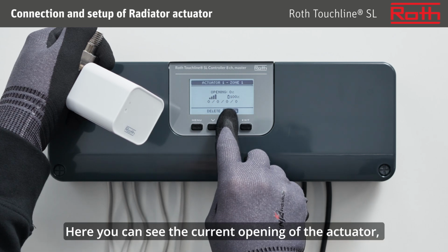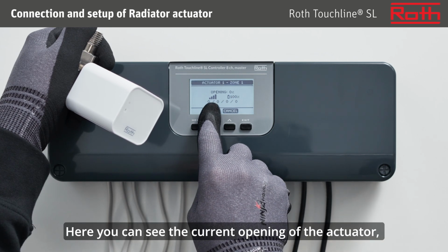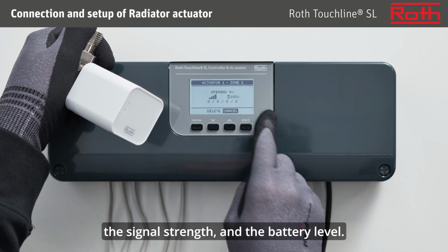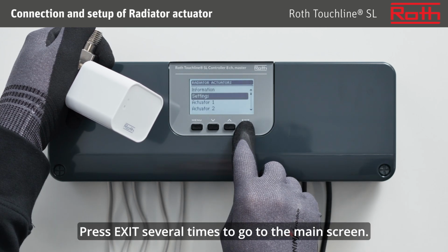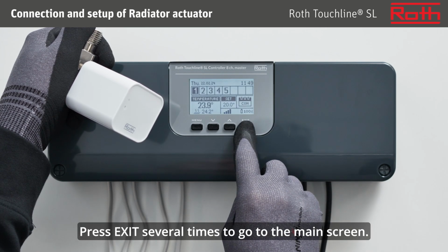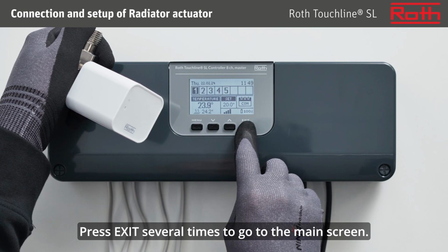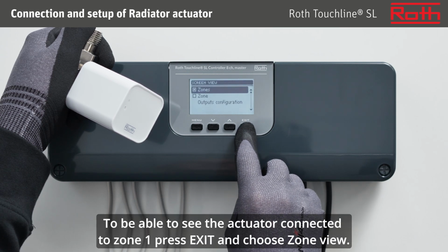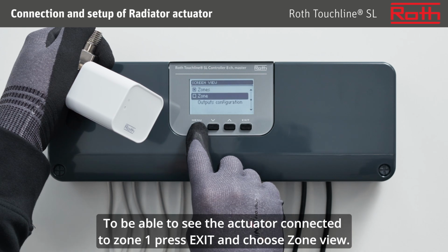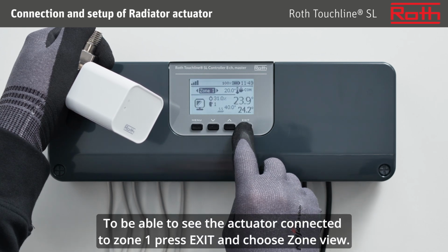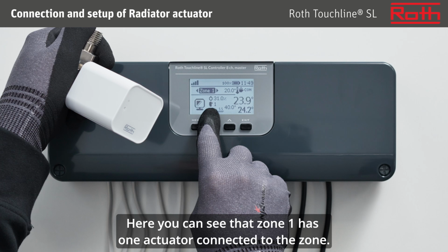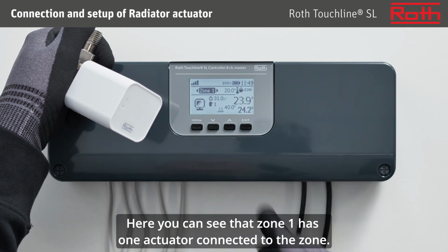Here you can see the current opening of the actuator, the signal strength, and the battery level. Press Exit several times to go to the main screen. To be able to see the actuator connected to Zone 1, press Exit and choose Zone View. Here you can see that Zone 1 has one actuator connected to the zone.